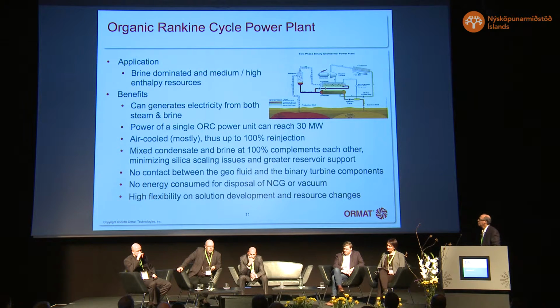The mixture of condensate and brine complements each other, so minimizing silica scaling and giving greater reservoir support. There is no contact between the steam and the binary fluid and the turbine blades. There is no need for energy to dispose the NCG, and throughout the years, due to changes in the resource, an ORC can easily be adapted to changing resource characteristics.